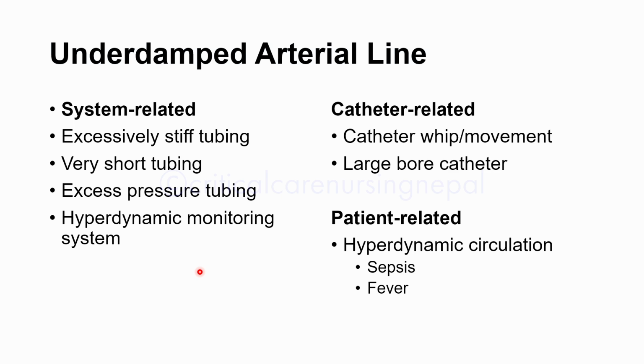And a very short tubing to the transducer can also lead to underdamping, and that is a system error. Excessive pressure tubing or hyperdynamic monitoring systems can lead to an underdamped arterial line. Catheter related, if there is a catheter whip or movement, and if the size of the cannula is large, then we can get more than 3 oscillations. And in patient related, if the patient has hyperdynamic circulation, as in sepsis, fever, or thyrotoxicosis, at that time also you can get an underdamped arterial line.